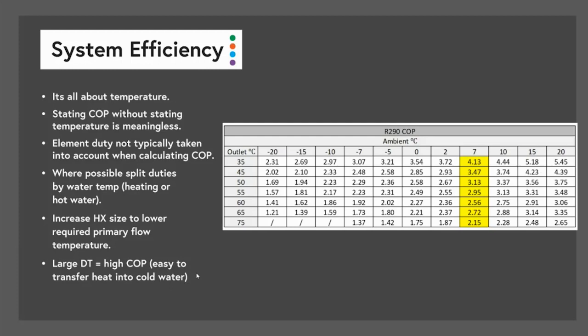Typically, underfloor heating would be run at around 45-degree flow temperature. And we might, in say this area of the country, Lower North Island, choose to look at an ambient temperature around 2 degrees, midwinter, worst case scenario. So you can see that if we take 2 degrees outside and 45-degree outlet temperature, that COP is now 2.9, or 290%. So considerably lower than the rated efficiency of that appliance. So that means that in real life conditions, the rated efficiency of the appliance is meaningless.